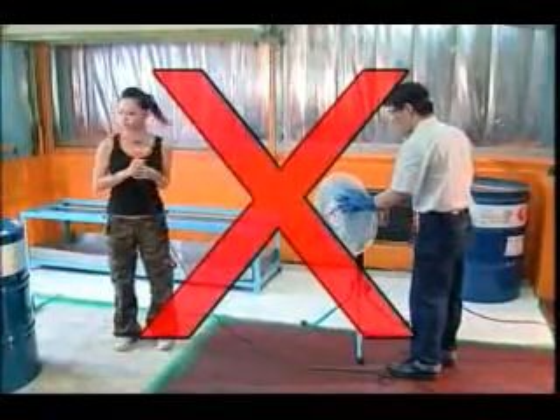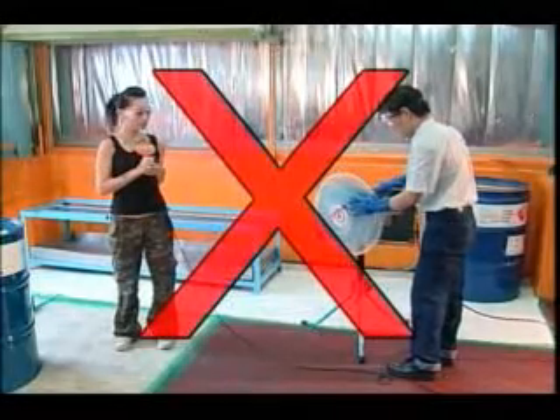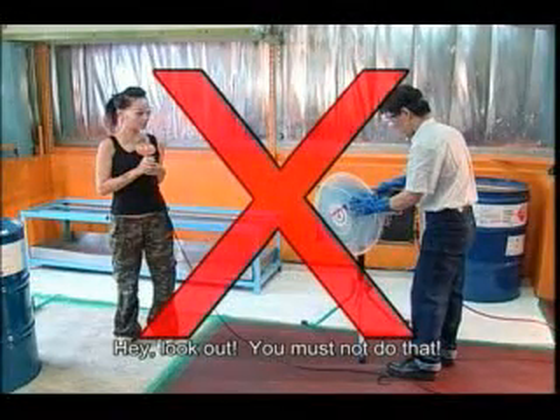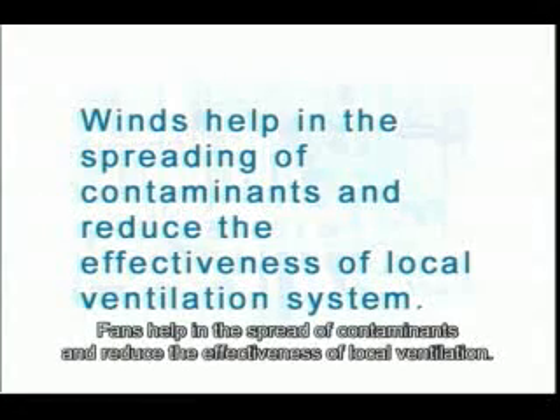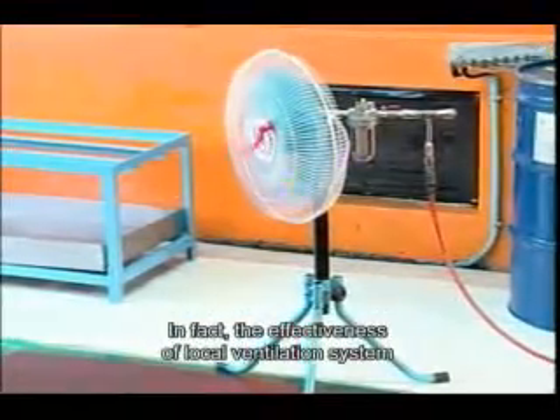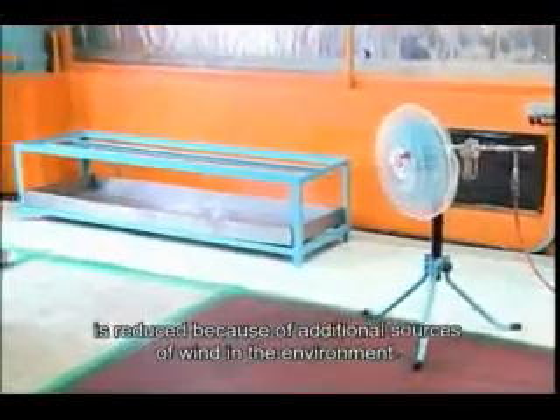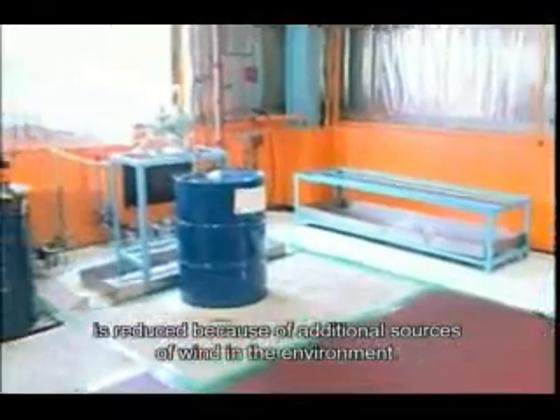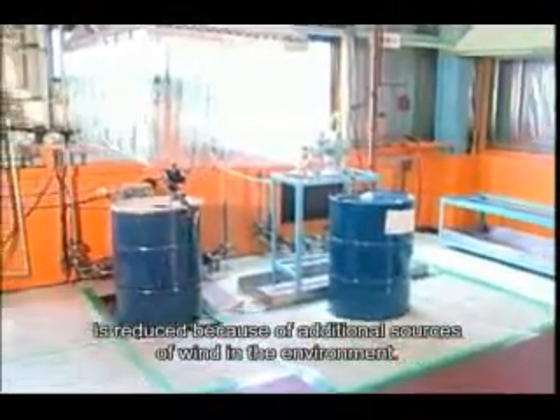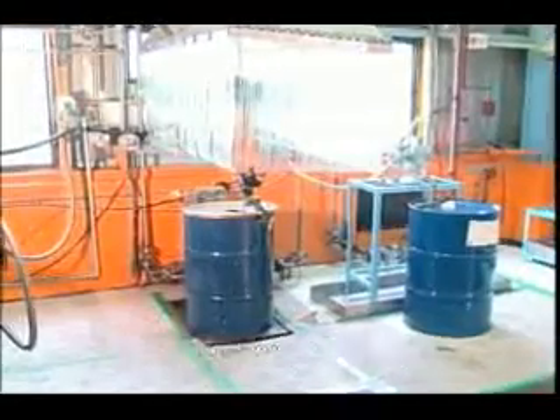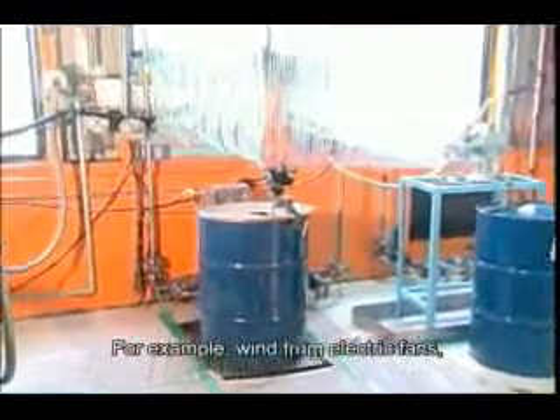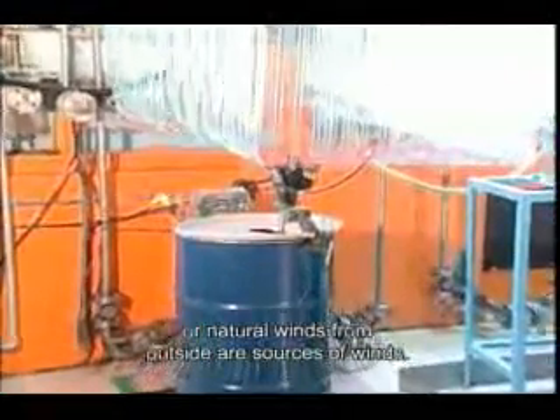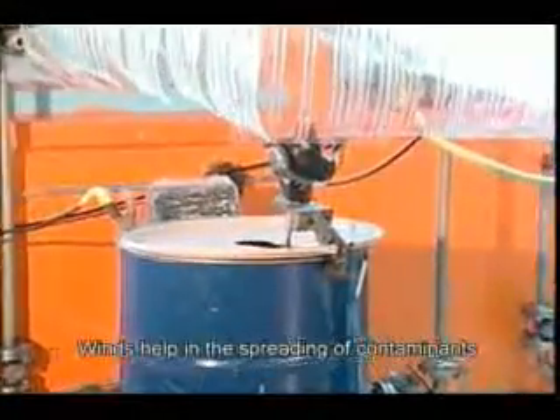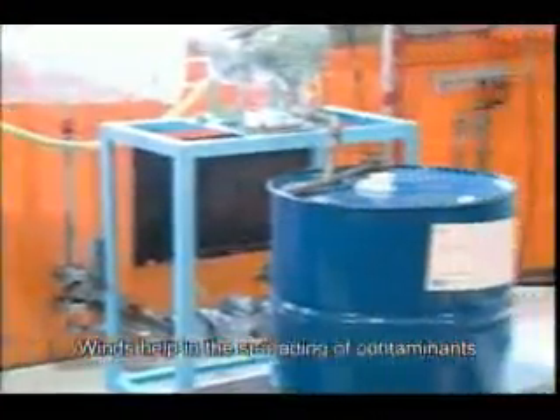Look out! You must not do that. Fans help in the spread of contaminants and reduce the effectiveness of local ventilation. In fact, the effectiveness of local ventilation system is reduced because of additional sources of wind in the environment. Where does the wind come from? For example, wind from electric fans or natural winds from outside are sources of winds. Winds help in the spreading of contaminants and reduce the effectiveness of local ventilation system.